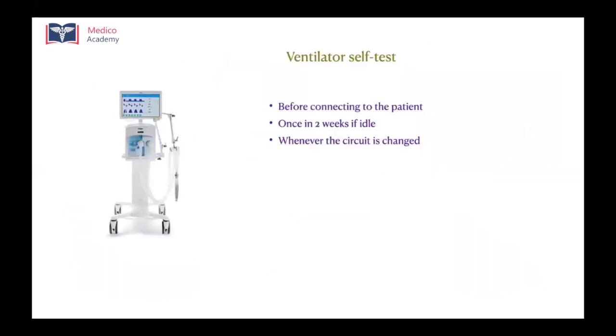So the next step would be the ventilator self-test. Now that you have connected the circuit to the patient and switched on the ventilator, the next would be a prompt from the ventilator itself to go for a self-test. So ventilator self-test is to be conducted before connecting to any patient. If the ventilator is lying in one corner for a few months or days, then you need to check it once in 2 weeks to see that the ventilator is working fine. Or the third indication is whenever the circuit is changed.